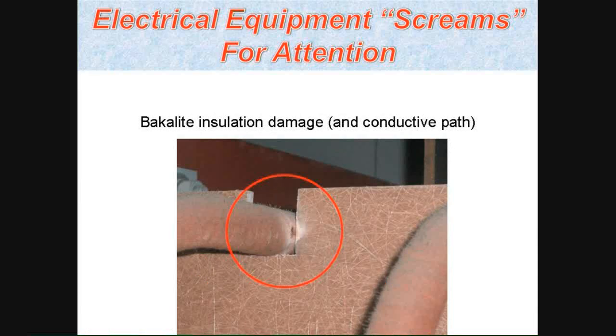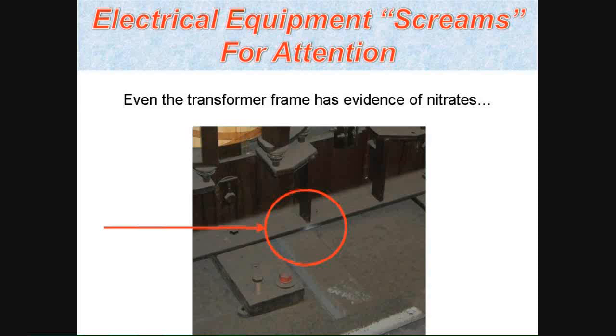Even here, the discharge was more evident. This is one of the conductors running through a Bakelite phase barrier or insulator. It had actually had visual evidence of carbon indicating an electrical discharge across this Bakelite. It's only a matter of time before this ends up failing. And that was evident there. This is the transformer enclosure, and even on the structural support, there was evidence of nitrates. So this has been going on for quite some time. It's obvious it's in need of some housekeeping, but it's not the type of component you like to open up, energize, and work on. It gets kind of dangerous at those voltage levels.